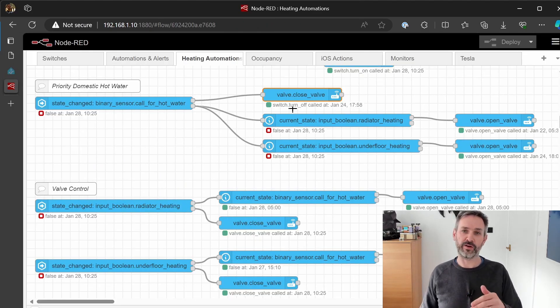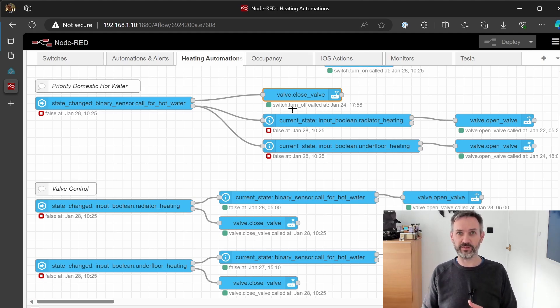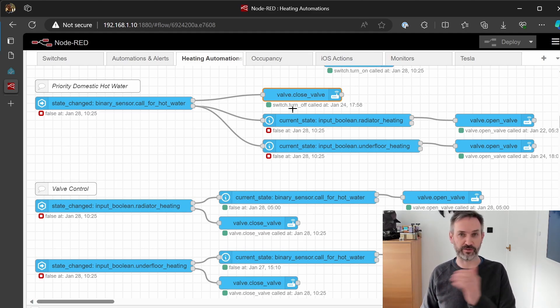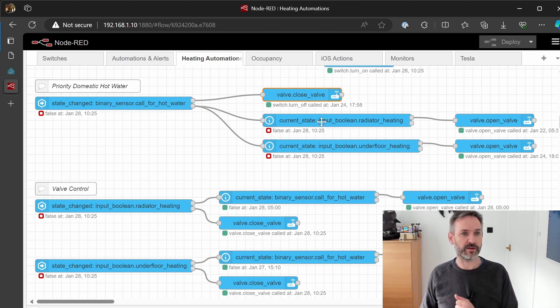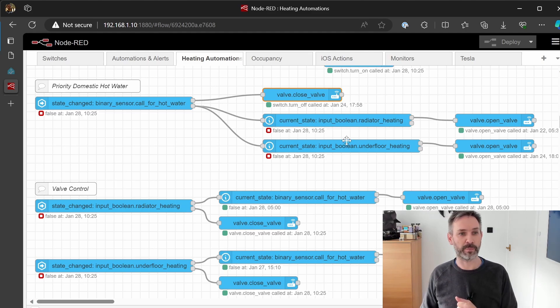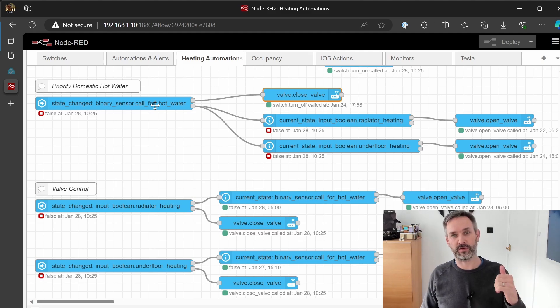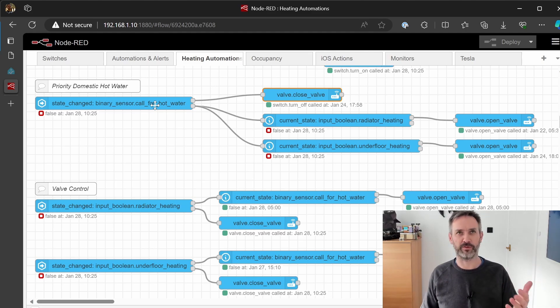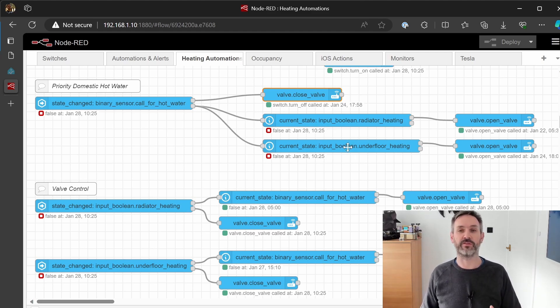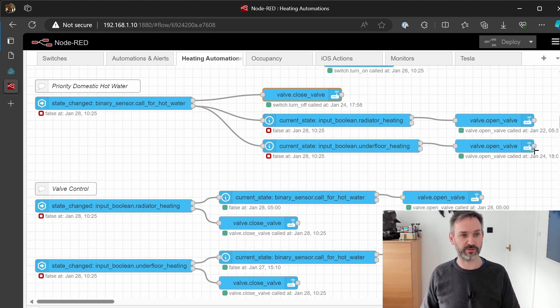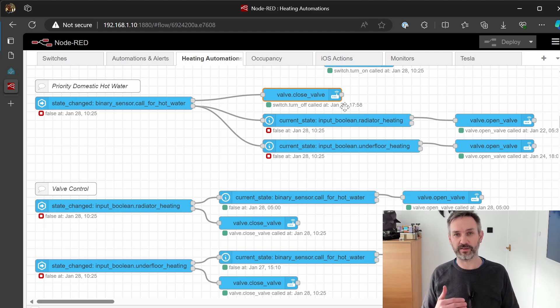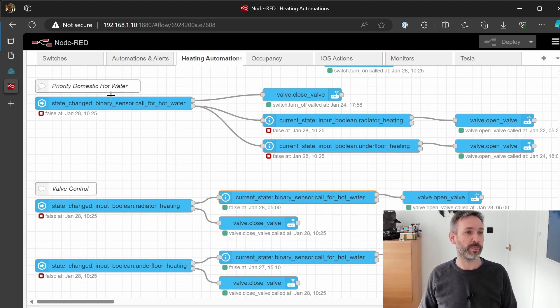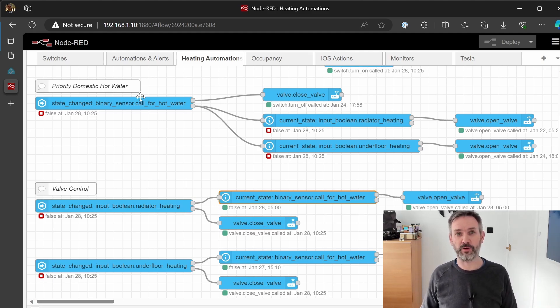Now when the call for hot water finishes, if the heating was already on we need to make sure that we turn on the heating when we open the zone valves and turn the heating back on. This is where my little virtual switches come into play. If they're set to true for either one, either the radiator heating or the underfloor heating, it'll then simply open the valve. So when a call for hot water finishes it will check to see if the thermostat wants the radiators on or if the thermostat wants the underfloor heating on and if it does it'll just open those valves again so it'll essentially remember what way the heating was before. The hot water valve will actually close the heating valves if they're open but it will remember to reopen them once it's done.